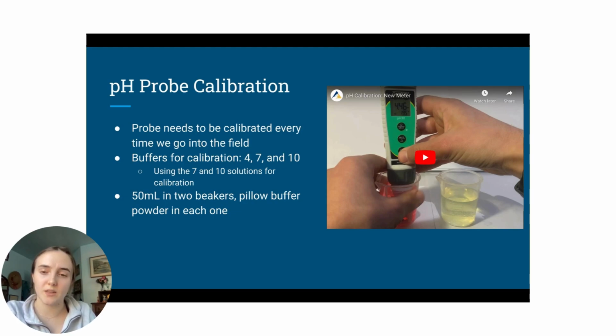pH can vary depending on landscape, bedrock type, and a few other factors. In our region, we find the pH to be at or above 7, so to calibrate the probe, we'll be using buffers of pH 7 and pH 10. If the pH tends to be lower than 7, then the second standard to calibrate the meter to is pH 4.